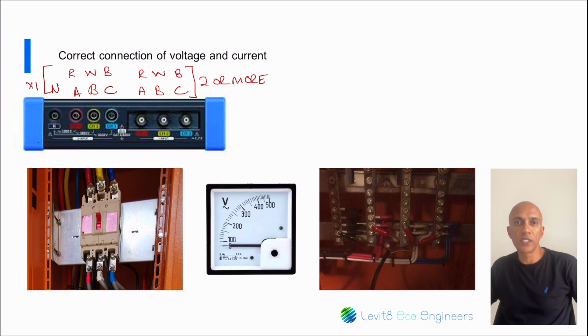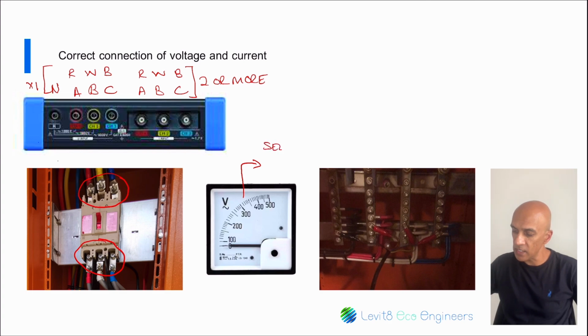Now, single-phase instruments are not very common, but are available and are more likely to be used for measuring house loads and consumption. For voltage measurements on low-voltage systems, you would connect your voltage clips to either the circuit breaker terminals, as you see in this picture, or you could connect them onto the voltmeter. So your voltmeter would usually have a selector switch at the back, and you could connect onto each of the phase voltages on that selector switch, or directly onto the bus bars of the relevant phase.